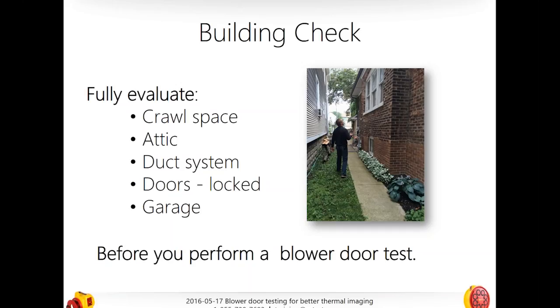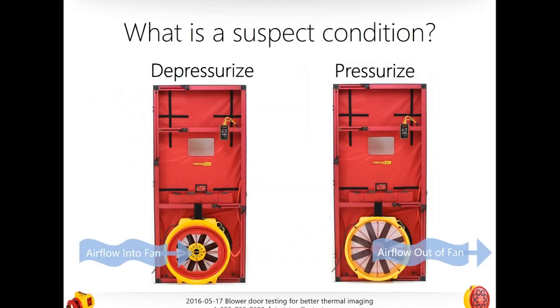First, just like a regular test, you want to do a building check. It is absolutely critically important to do a full evaluation — not just for health and safety and to know how to set up the house, but if you're going to do a thermographic check and you don't understand how the house is built, what's inside, what's outside, where the thermal boundary is — you will have an almost impossible time interpreting your thermographic images.